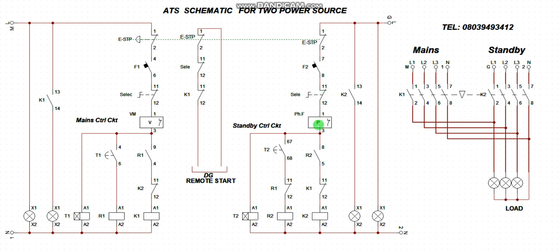All right, then from there, there's what we call phase failure. In a generating set, it's supposed to have a three-phase supply to your load. If one phase is having an issue, there is a phase failure, and this device will not enable the contactor to close. So you should come and rectify why the three phase is not complete. That is the sense of putting this phase failure. When the three phases are complete, you are going to have output from this device. Now the supply goes to my timer. The timer starts counting.